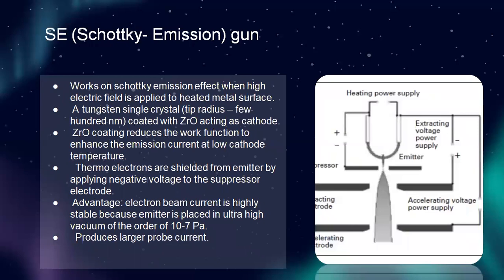The third type is the Schottky emission gun, which works on the Schottky emission effect when a high electric field is applied to a heated metal surface. A tungsten single crystal tip of radius a few hundred nanometers coated with ZrO acts as cathode. The ZrO coating reduces the work function to enhance emission current at low cathode temperature. Thermoelectrons are shielded from the emitter by applying negative voltage to the suppressor electrode. Advantage: the electron beam current is highly stable because the emitter is placed in ultra-high vacuum of the order of 10⁻⁷ Pascal, producing a larger probe current.